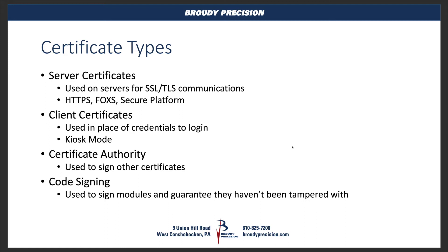Client certificates sort of take this and flip it on its head — they basically replace what we typically think of as credentials to log into a server. So instead of having a username and password, you could have a certificate to log into that server. This is used a lot in IT for things like SSH. But in our Niagara space, they can be used for a pseudo-kiosk mode where a user wouldn't have to log in. The browser on that screen would already have this certificate in it, and Niagara would know that when anyone signs in with that certificate, it knows who that user is and what they have access to.